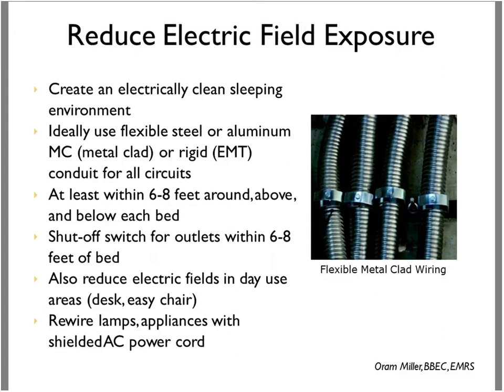Here's what we can do to help mitigate this: create an electrically clean sleeping environment. Ideally, use flexible steel or aluminum metal-clad flex or rigid conduit for all circuits, at least within 6 to 8 feet around, above, and below each bed.